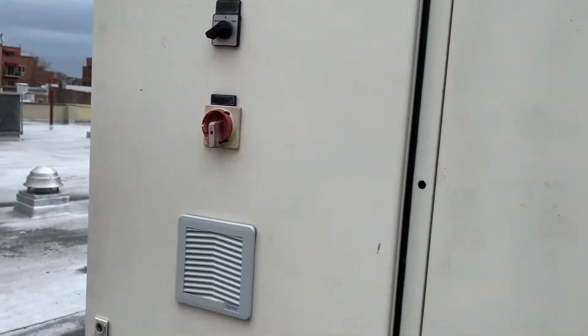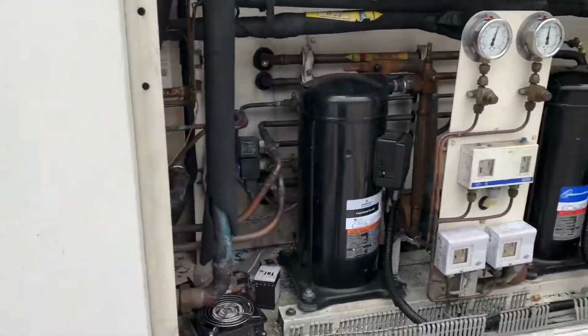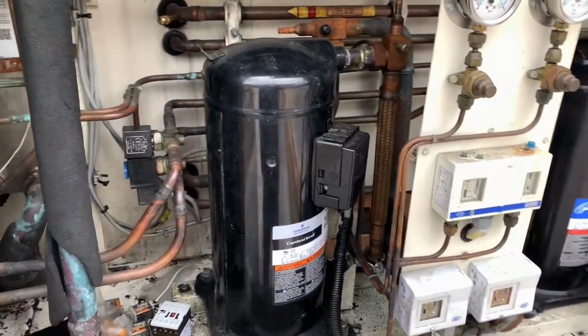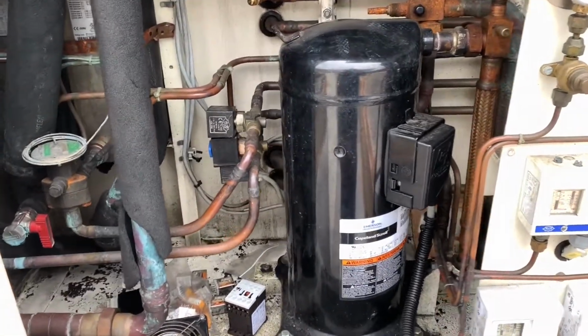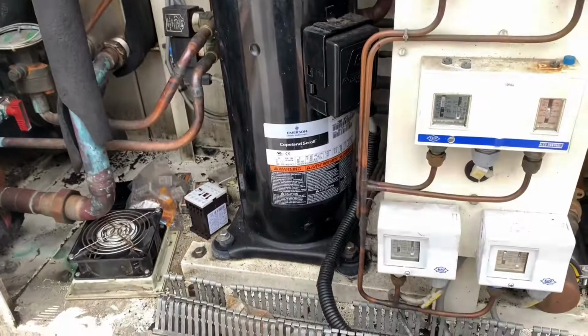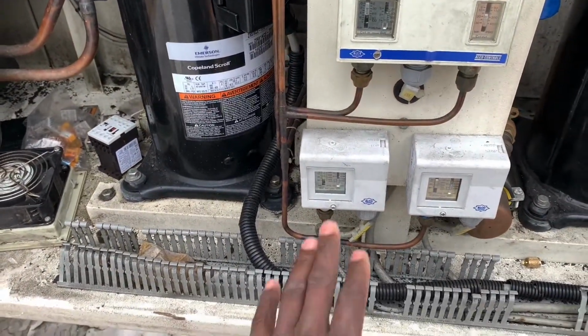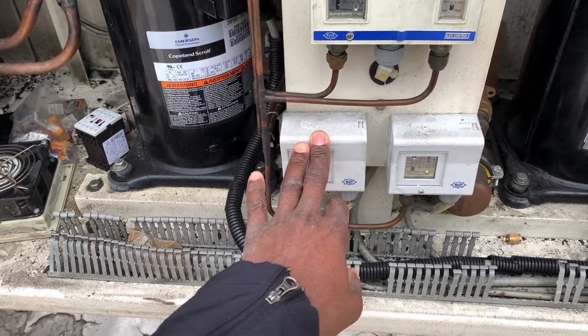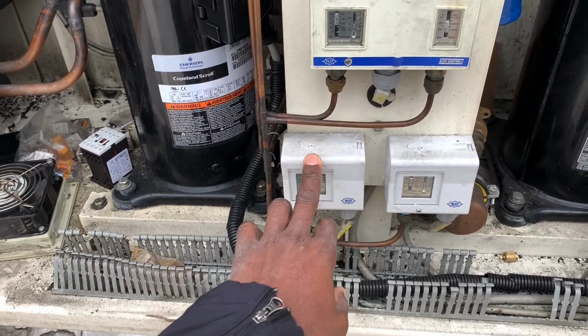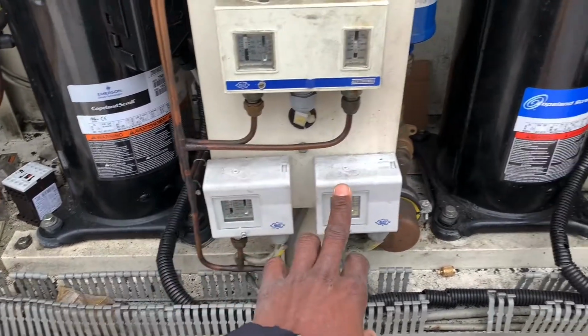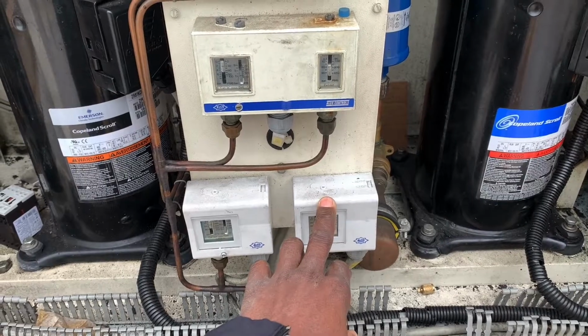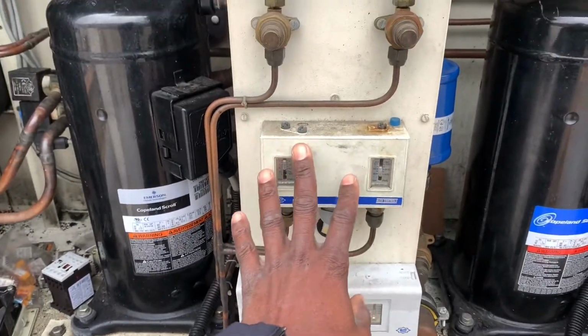So as you can see, it's maintaining the temperature within 0.4 of a degree C of set point. Here is your fan cycling switch for the low speed of the fan, and fan cycling switch for the high speed of the fan. And this here is your high and low pressure safety.